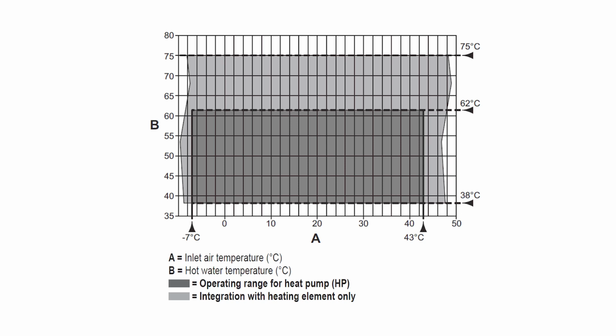This is really good, as within the operation, water could be heated up above the disinfection temperature within the heat pump alone. If the temperature falls outside of this scope, the heating element provides a backup. The immersion heater helps achieve a maximum water leaving temperature of 75 degrees C. This gives you peace of mind knowing that water could still be heated should the temperature fall below -7 degrees C.